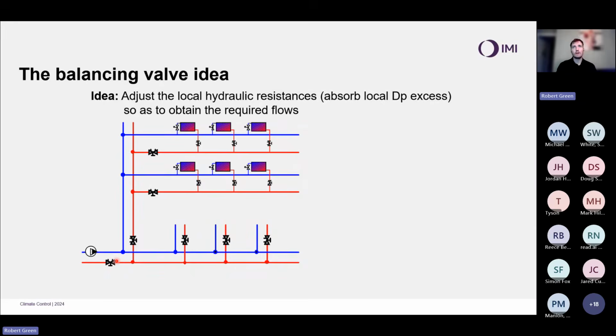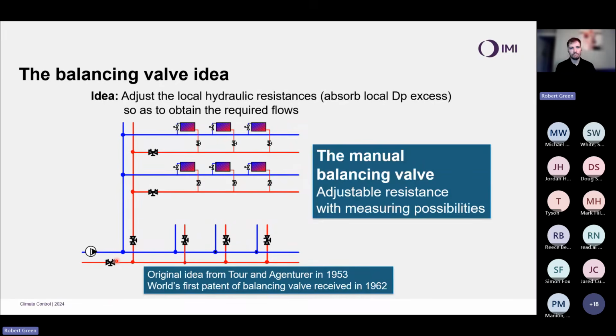And the idea with this is we're going to be using a manual balancing valve. And what a manual balancing valve does is it allows me to adjust my resistance and physically measure the flow that I'm adjusting to. So with a manual balancing valve, I can adjust this valve to take out the difference between the flow going here or the flow going up here. And I can effectively force the water further down my system by making it relatively more difficult to go up that first riser. As I said, water's fundamentally lazy.